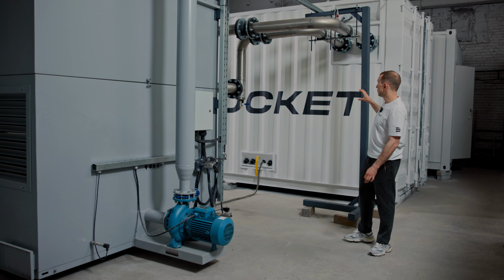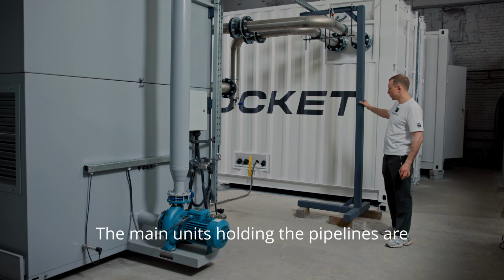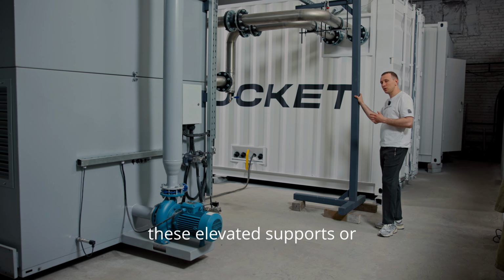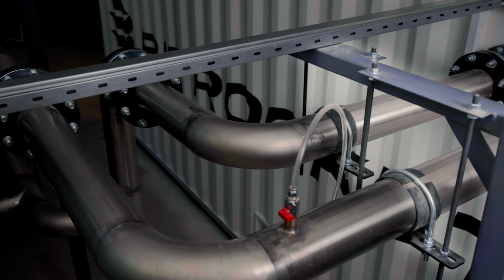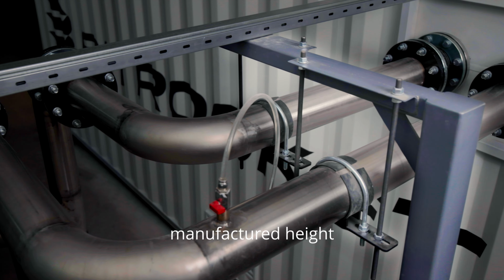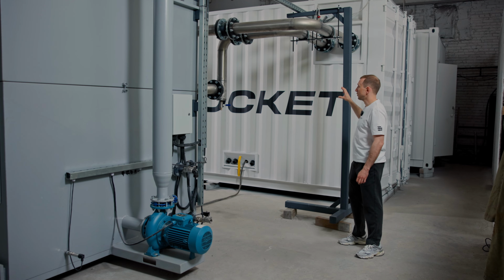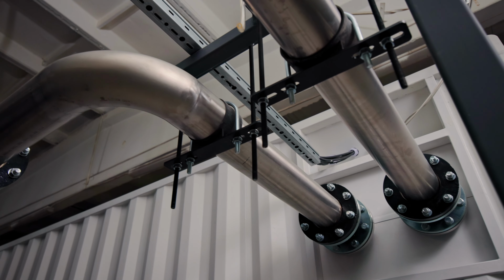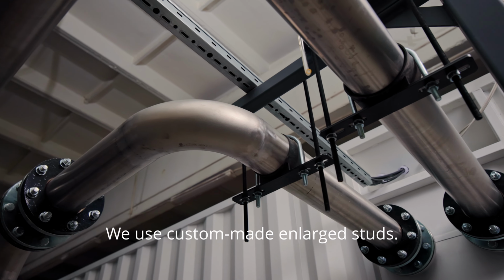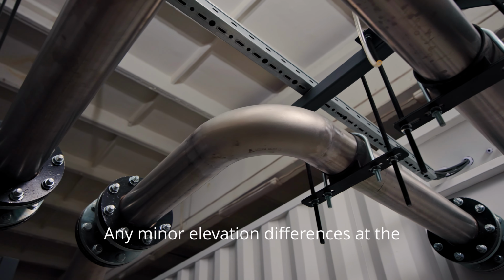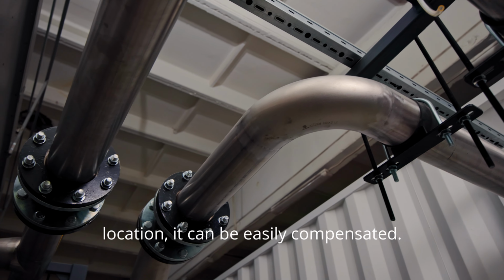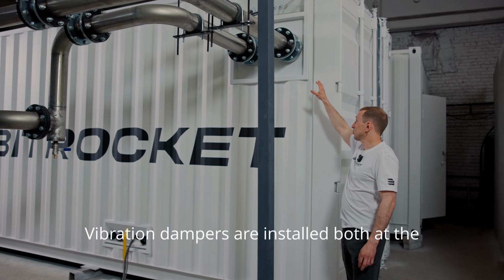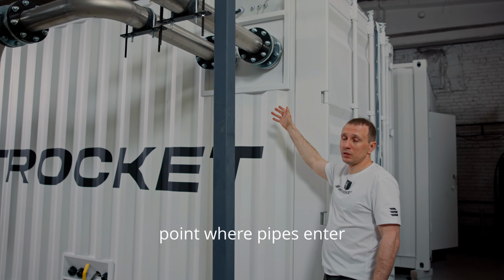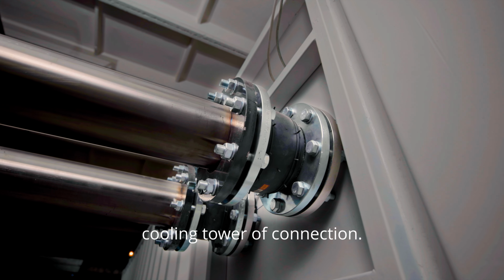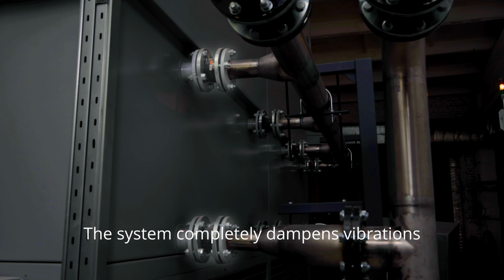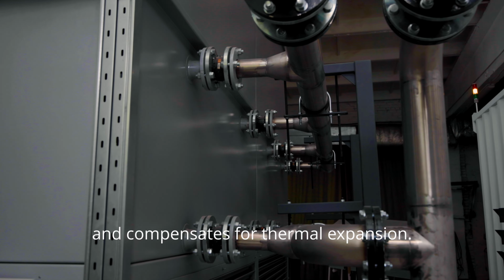Connection of the cooling tower. The main units holding the pipelines are these elevated supports, or as we call them, trestles. The pipes are supported by specifically manufactured height-adjustable suspensions. Here you can see the threading. We use custom-made enlarged studs. Any minor elevation differences at the location can be easily compensated. Vibration dampers are installed both at the point where pipes enter the container and at the cooling tower connection. The system completely dampens vibrations and compensates for thermal expansion.